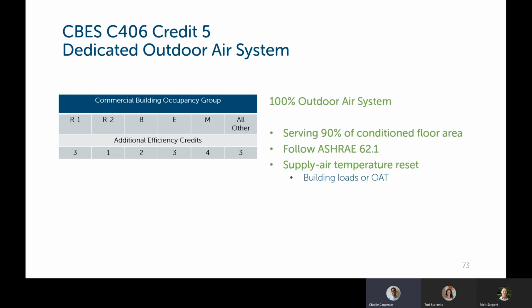You can install a dedicated outdoor air system in your building. That's always 100% outdoor air being supplied to the building at all times. You must be serving 90% of the conditioned floor area with this dedicated outdoor air system, and you have to follow the requirements of ASHRAE 62.1 2016, and that includes supply air temperature reset of the air coming from that dedicated outdoor air system based on the building loads or outdoor air temperature.